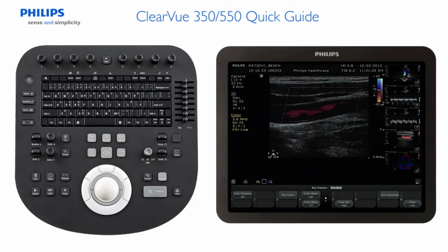Adaptive is a control used to enable the system to modulate the transmit frequency, depending on the image focal depth. This is helpful to increase color sensitivity in the far field. Adaptive can be applied by pressing Next, then the Adaptive Quick Key.